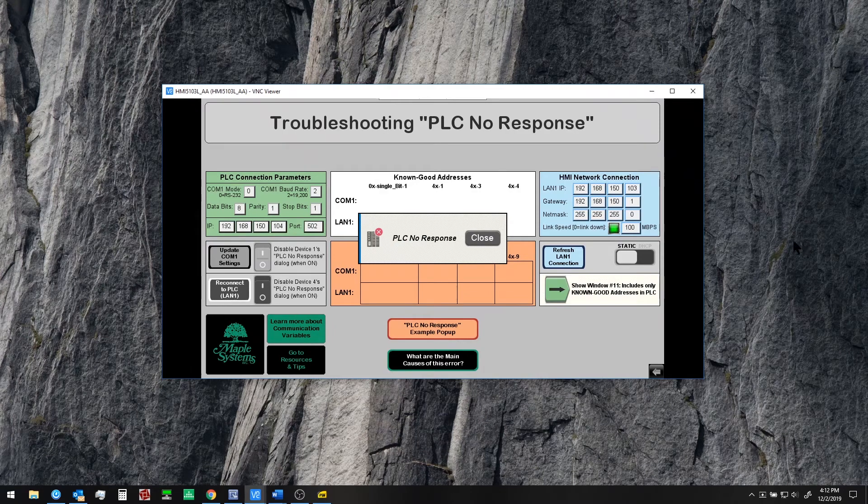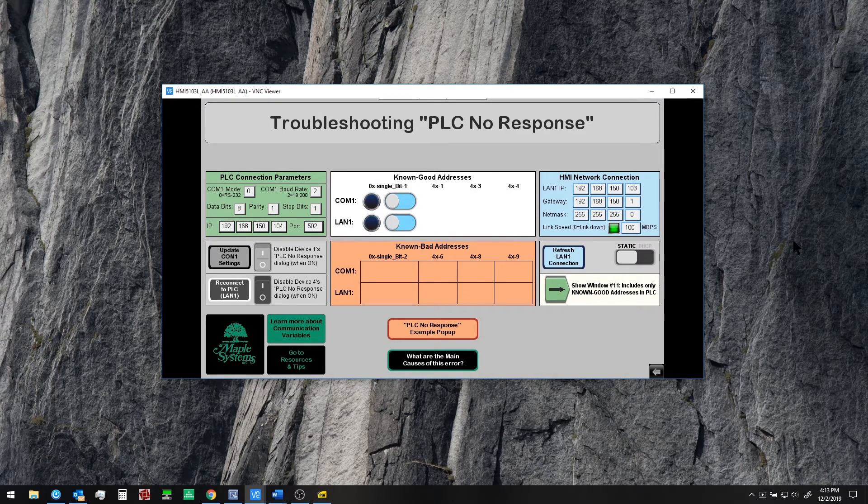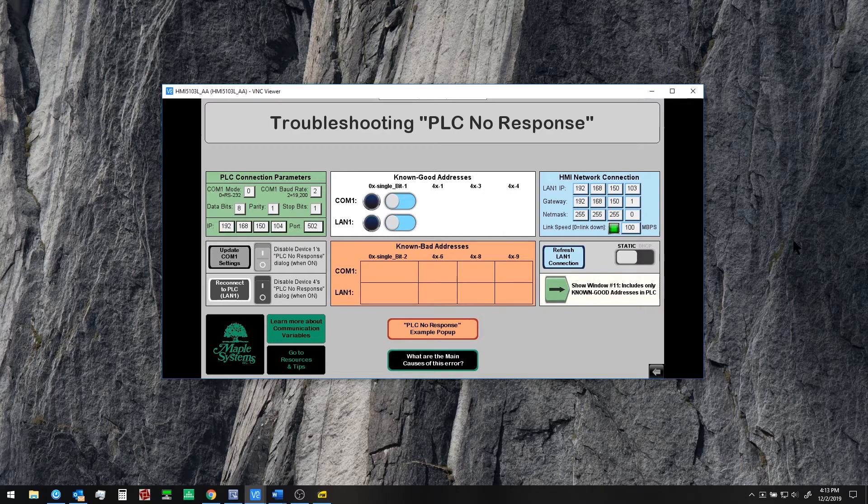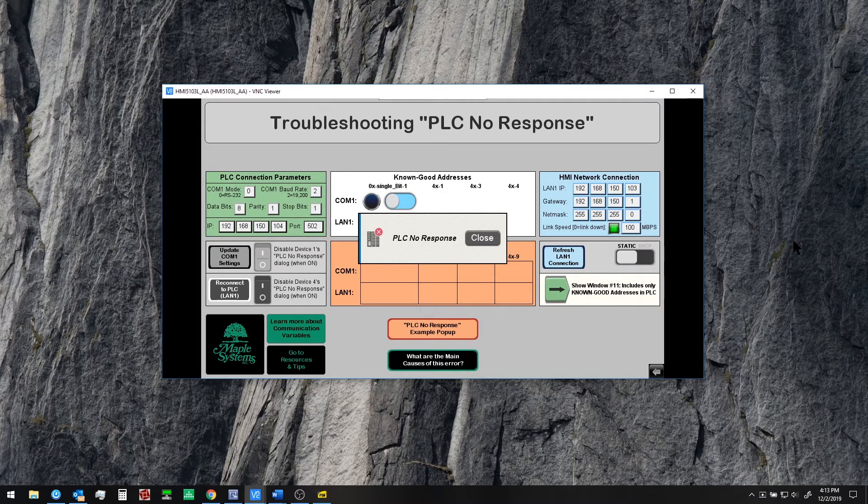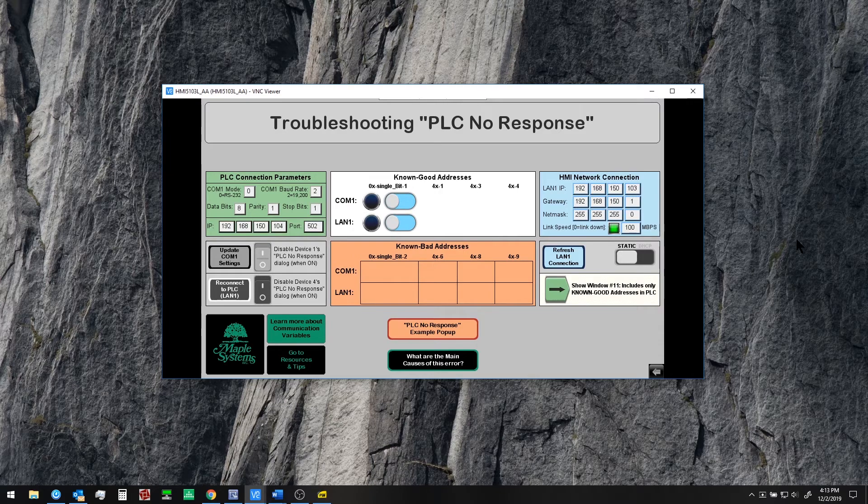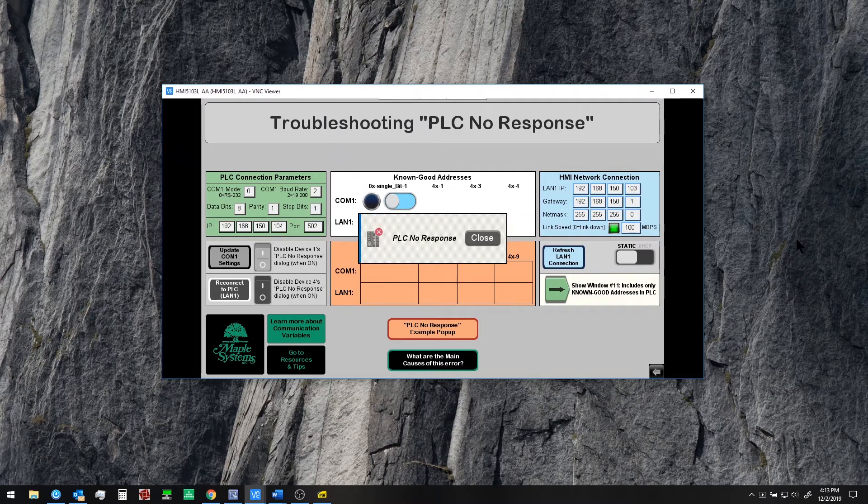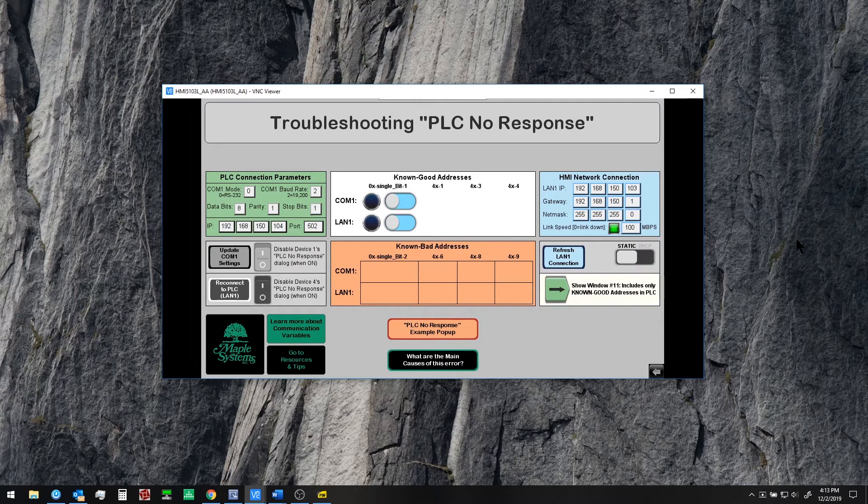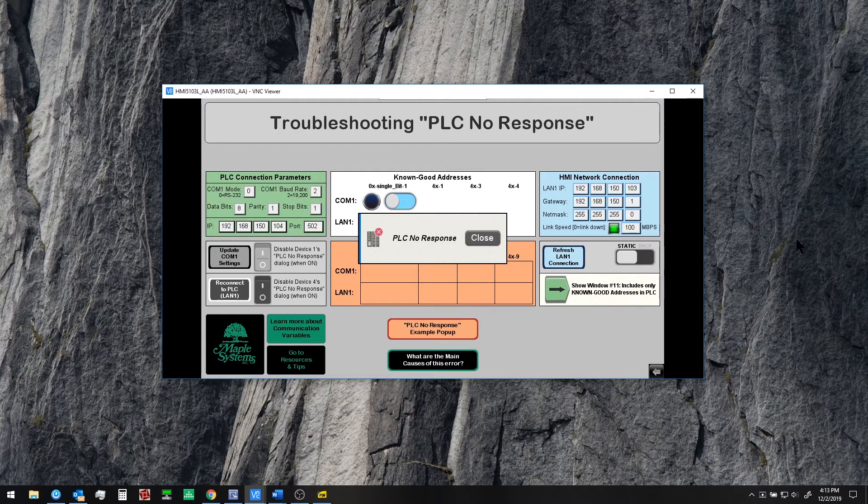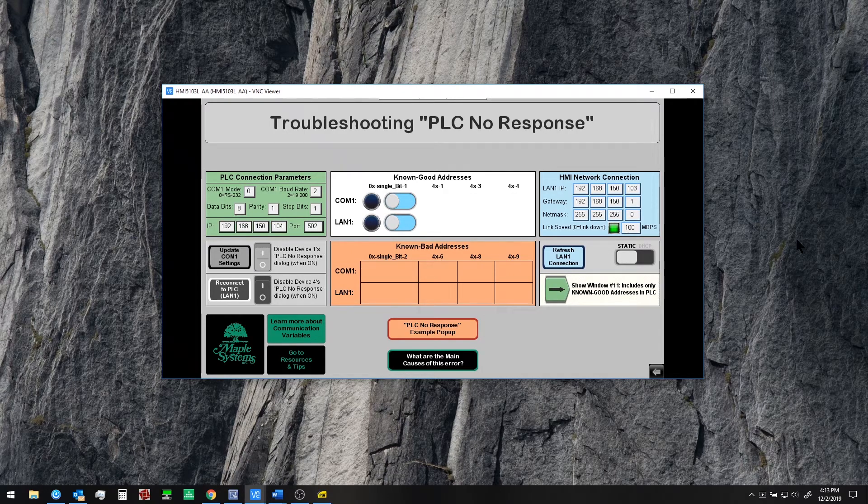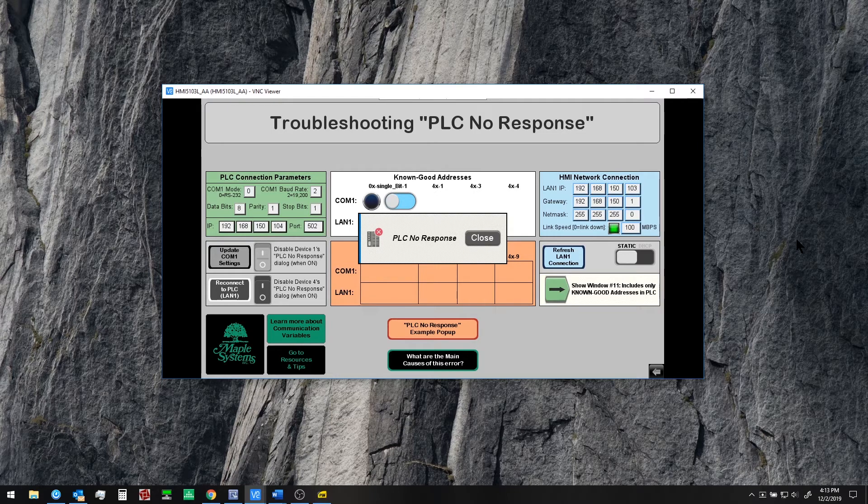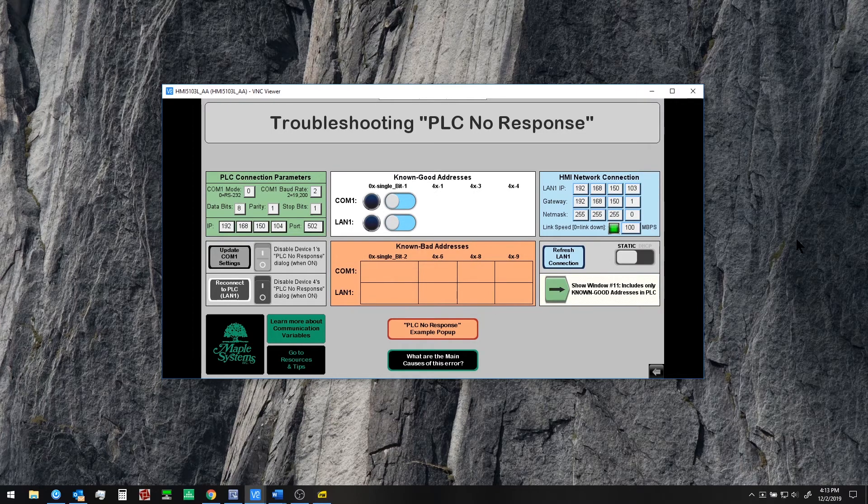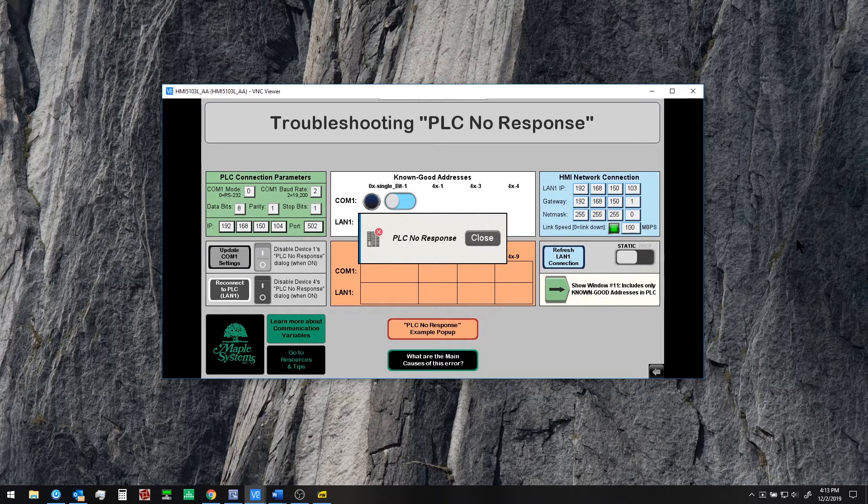Now you'll see the PLC no response message pop up here and it will continue to pop up every couple seconds and on this window running on the HMI we are missing some objects. This is common when you have an addressing issue that if any of the objects on the window are referencing an invalid register in the PLC most likely all of the other objects will disappear. The only exception here is that a toggle switch and bit lamp are still showing.